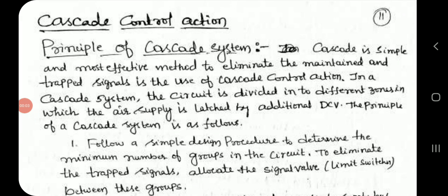Cascade control action. Principle of cascade system: Cascade is a simple and most effective method to eliminate the maintained and trapped signals. This is done by the use of cascade control action. In a cascade system, the circuit is divided into different zones in which the air supply is latched by additional direction control valves.